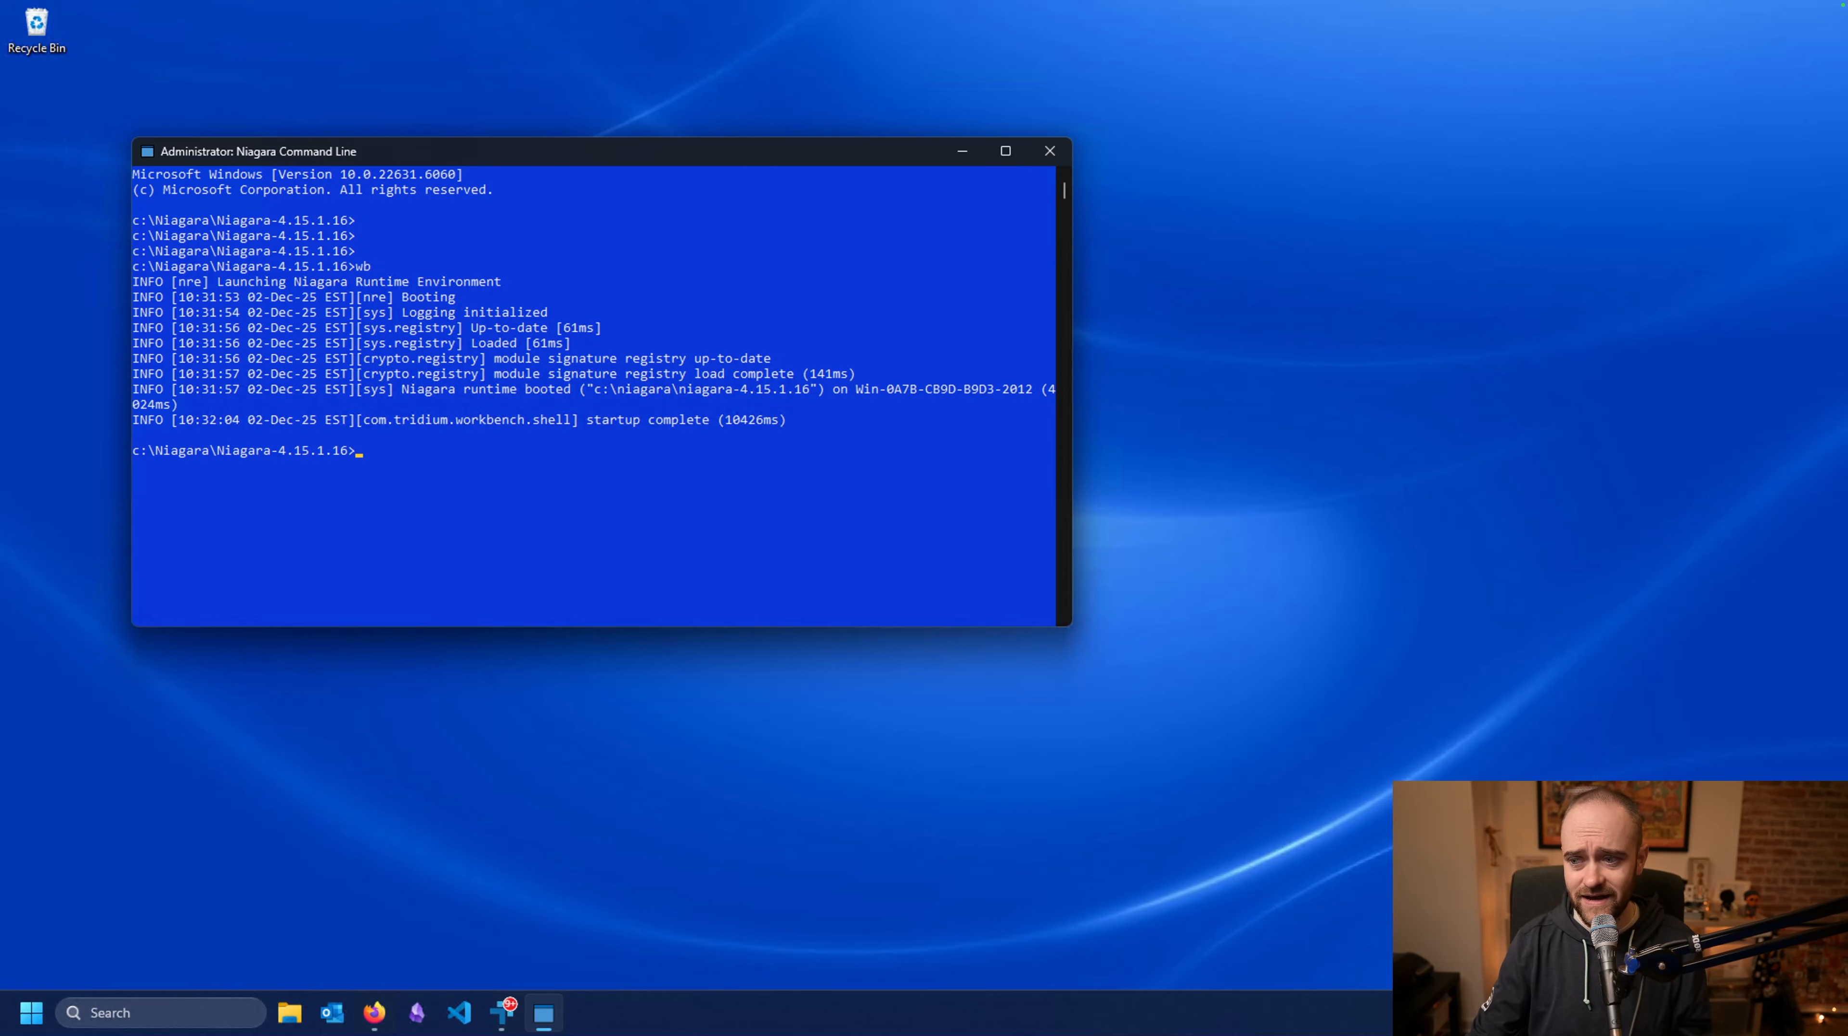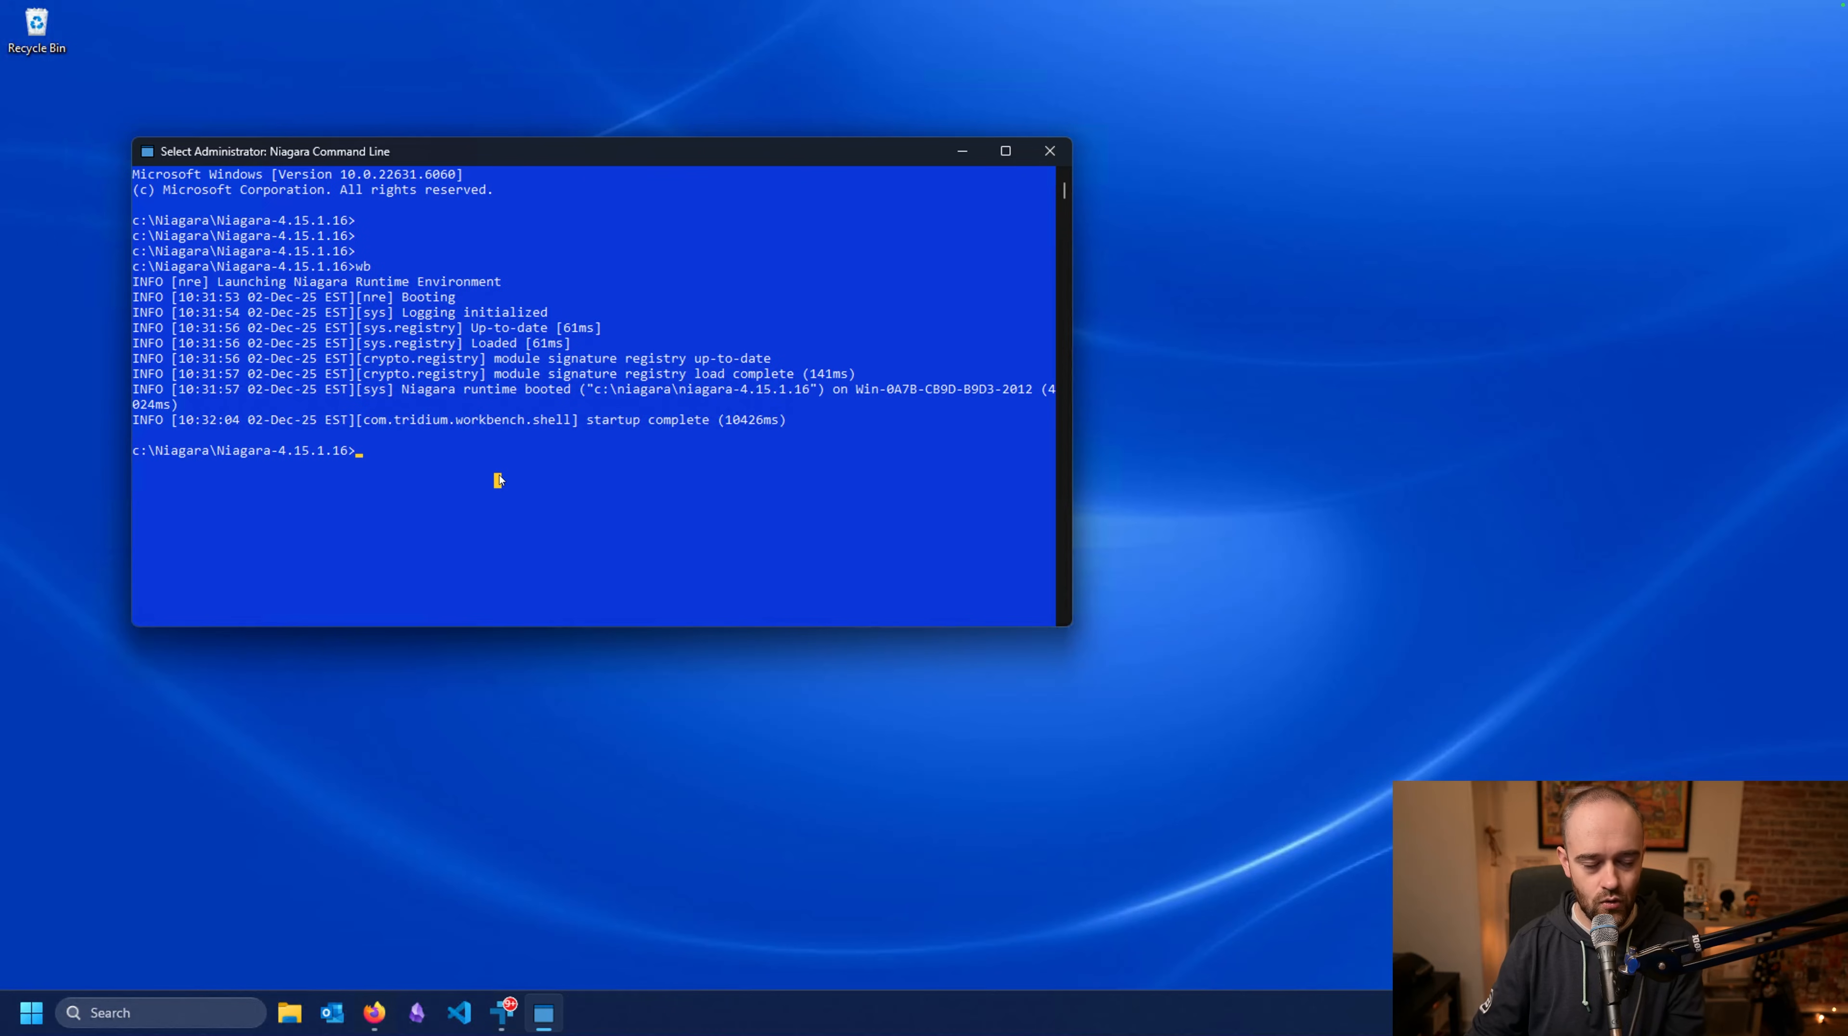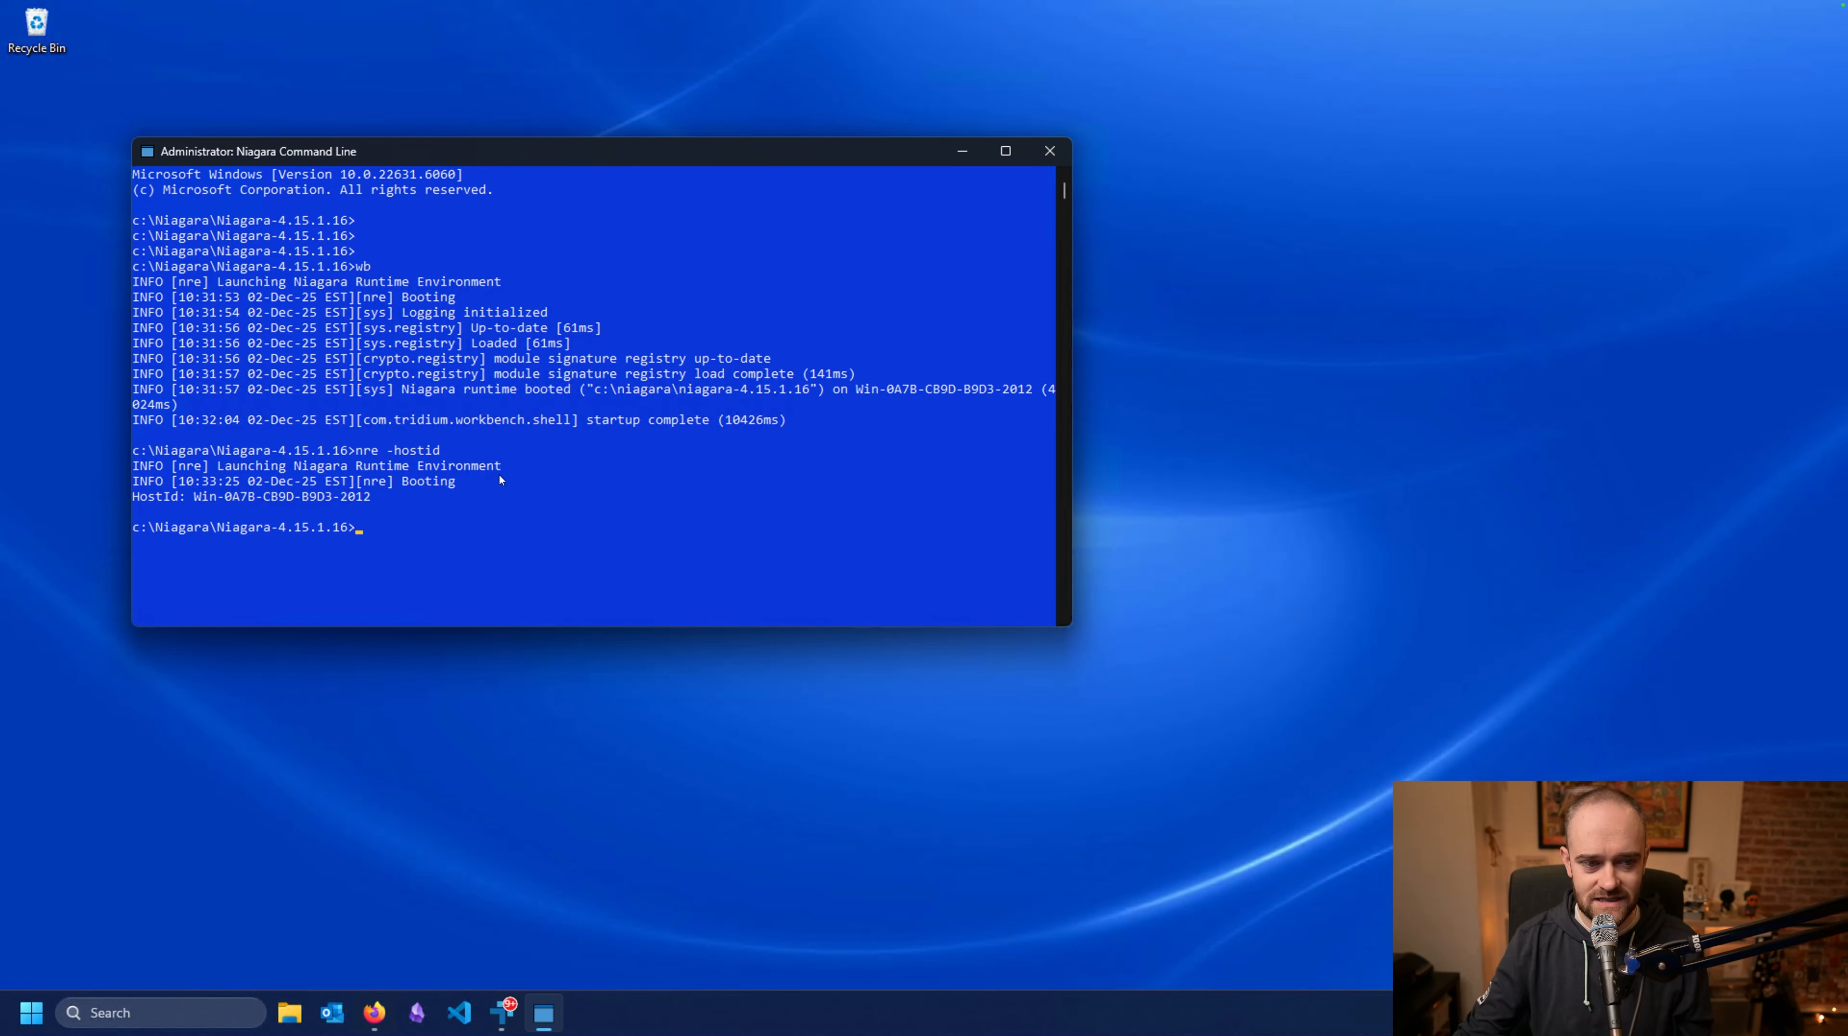We have some other commands we can also run here that will make our life a little bit easier when it comes to getting licensed. So if you went and ran your Workbench and maybe you didn't get that host ID pop-up window, or if you needed to know the host ID quickly and easily from a particular install of Niagara, you can pull up the command line here or the console and you can do 'nre space dash hostid'. And it will run a couple things and then it will spit out our host ID directly. This is the host ID for my particular machine.